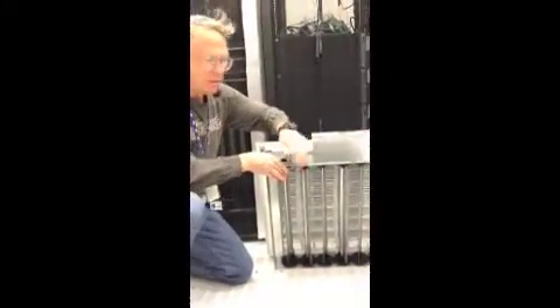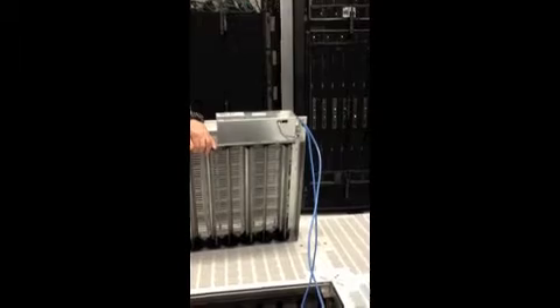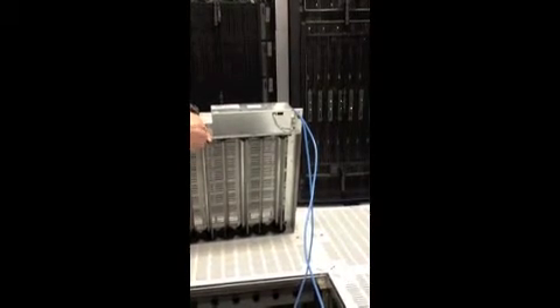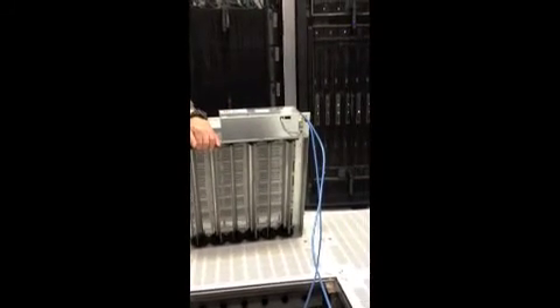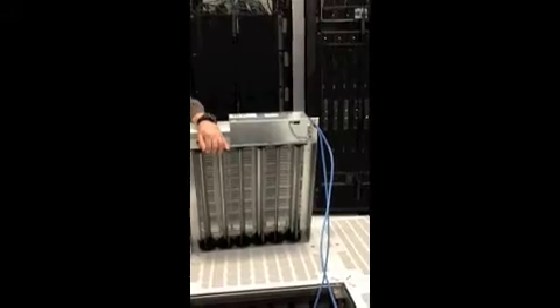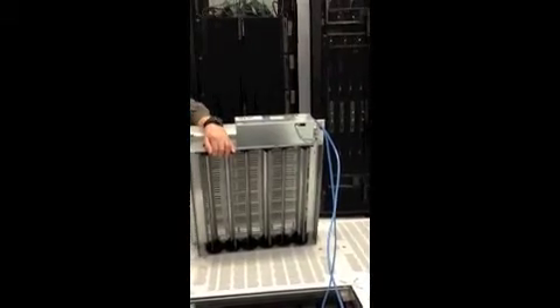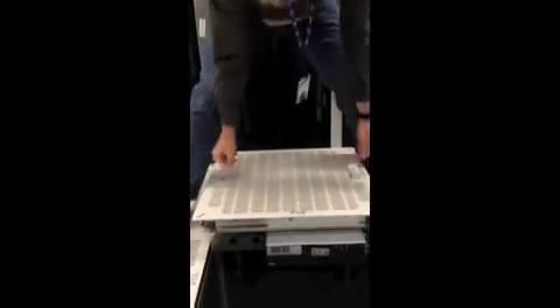The connection here, this looks like LAN cable, and it actually is, but this is really a serial Modbus connection, and they're just daisy chained together. So at the end of each row, we have a little transducer from Ethernet to Modbus for the control. Got a commercially available product yet? No.